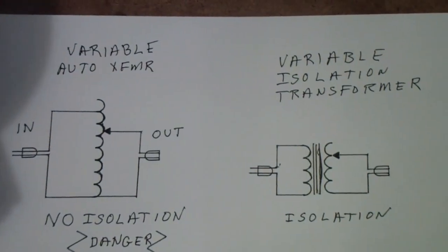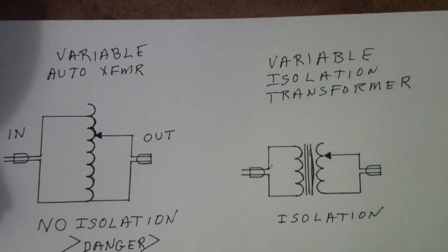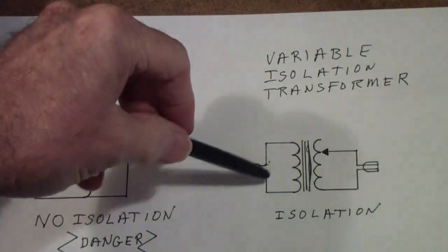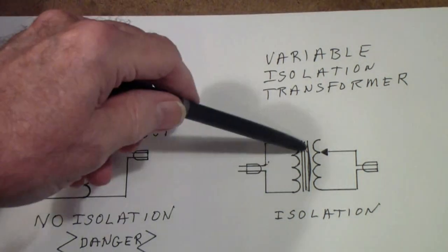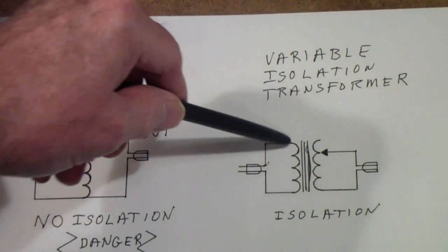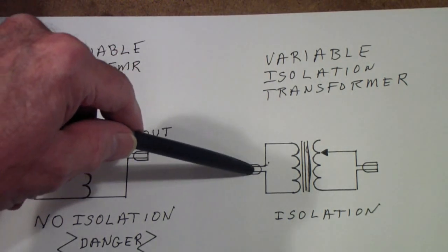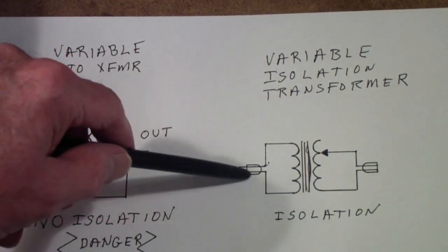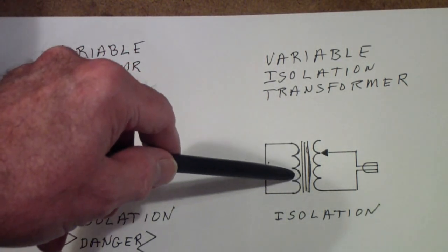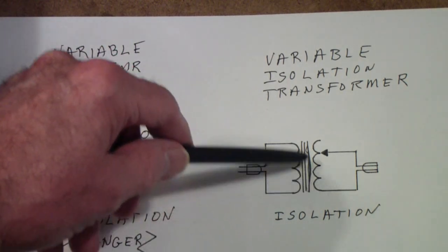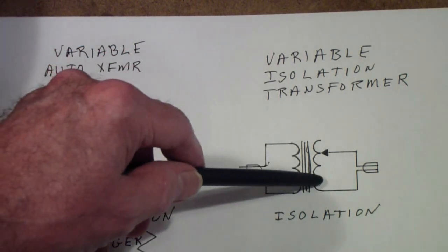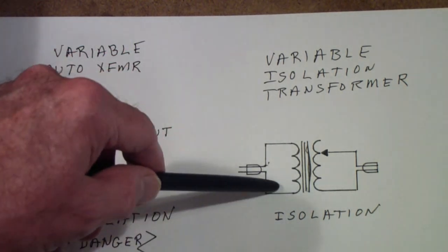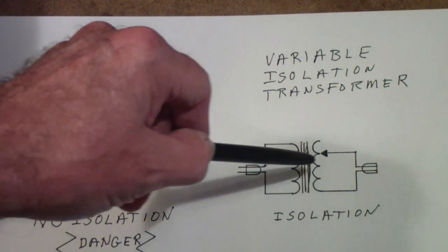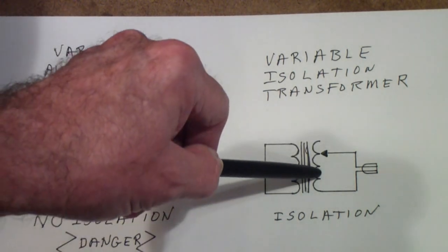If it's an isolated transformer, it will look like this unit over here. This is a variable isolation transformer. Notice that the AC line plugs into the primary. The only connection between the primary and the secondary is the magnetic fields that come through the core. No electrical connection from this side to this side, only magnetic.